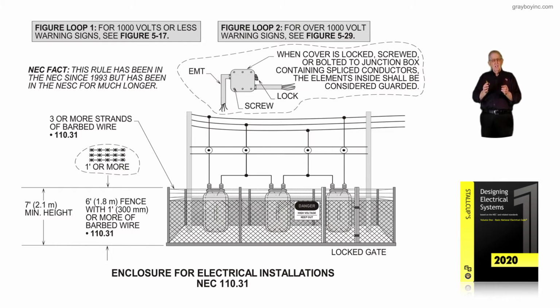Because once you entered into the substation, the high voltage terminals there would be naturally above the height, so when you walked in, you couldn't reach up and touch them. So they would have the height clearance required by the National Electrical Safety Code. And when you get into a utility-owned substation, it's the National Electrical Safety Code. But if it's customer-owned, then we are referred, in some cases, to the National Electrical Safety Code for clearances. Now, what we're trying to illustrate here: your fence is only, say, 6 foot, but we need 7 foot, as the code requires in NEC 110.31, because it's the owner of the facility.